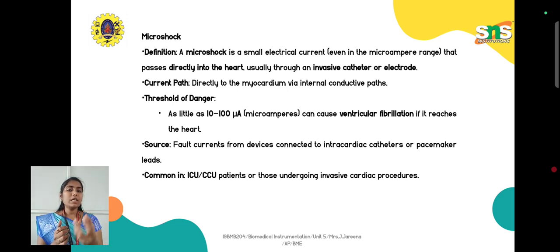So if there is any fault, short circuit or any kind of issue in the catheter, it will automatically affect the particular targeted area, which could be the heart or any other area where you are focusing. That is the main reason for the person to get a microshock when using catheters or electrodes.